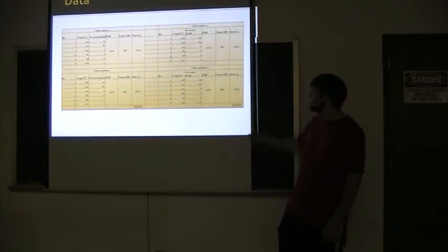So, okay, this is the data we took. We did 2 half-load runs and 2 full-load runs. And the time differences for the half-load runs weren't too similar. We had 119 seconds and 138, whereas the full-load ones are only a second apart. And for most of the calculations in this, we used the half-load run. And so they came up with an average time of 128.8 seconds. And the temperatures, pressures, RPM, and power, those were all fairly similar.